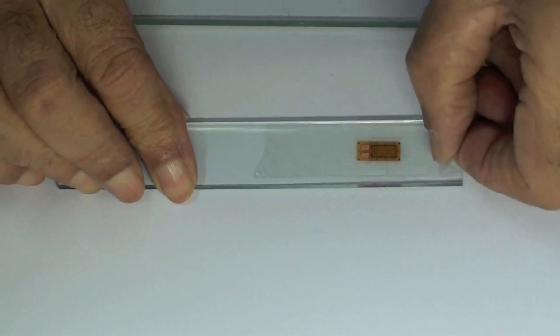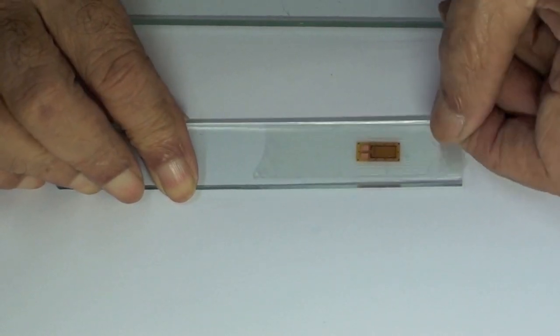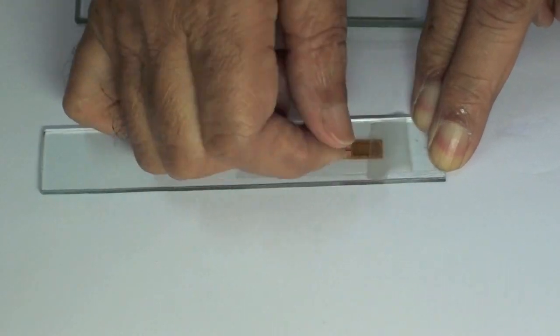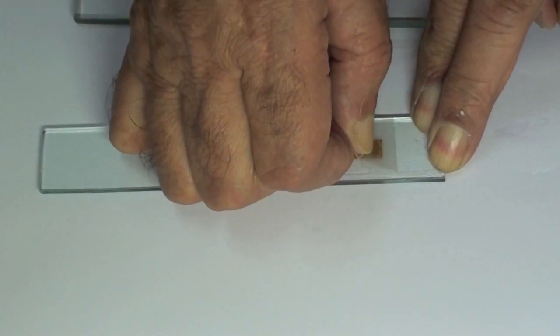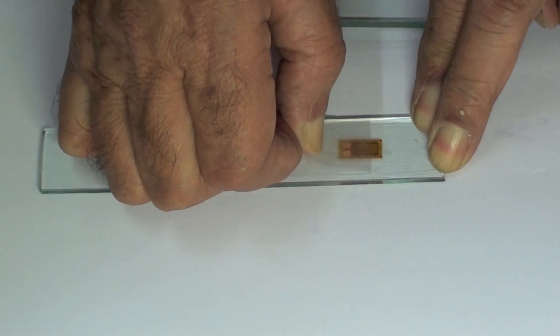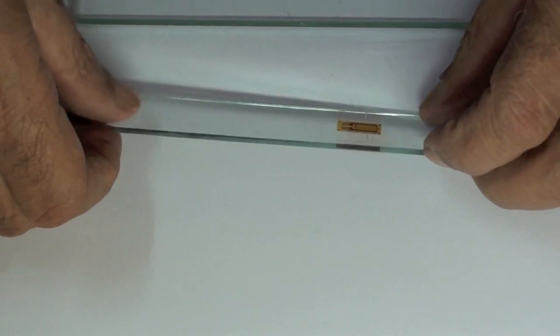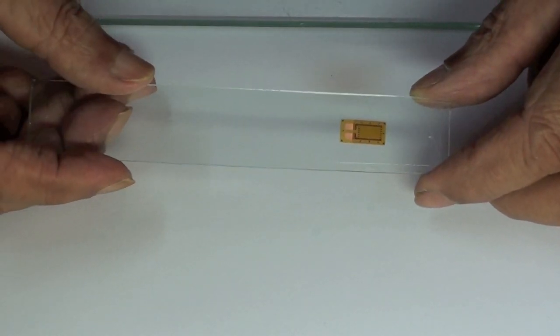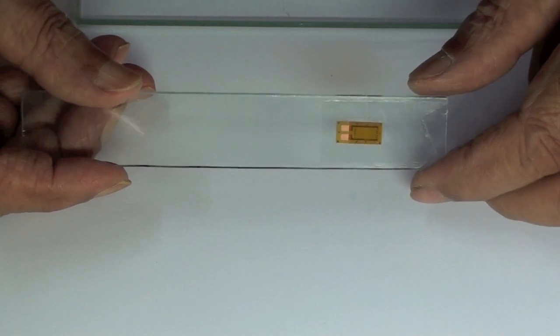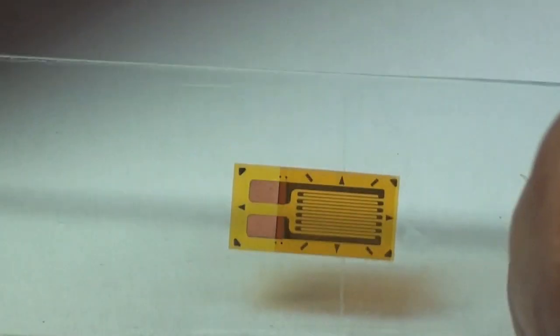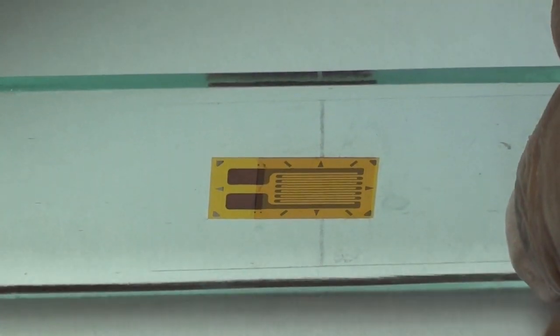Then the tape is removed by peeling it back on itself along the surface. The gauge is examined visually for any apparent defects such as unevenness or bulging or inadequate spread of the adhesive or air bubbles under the gauge.